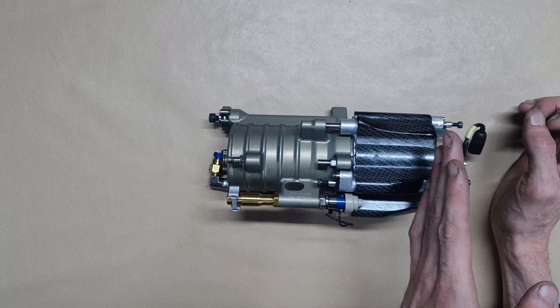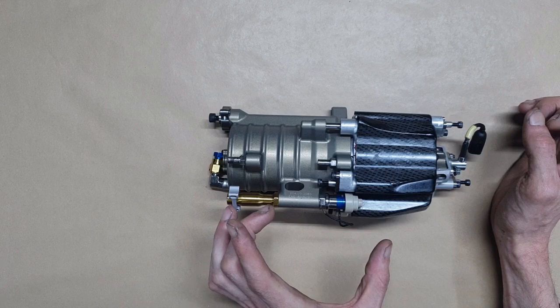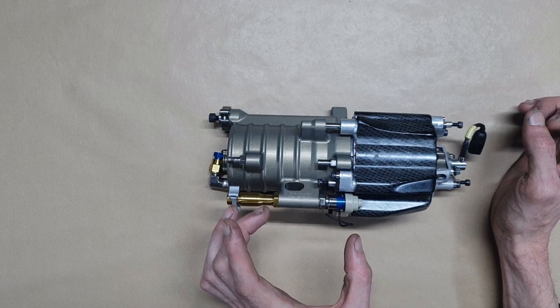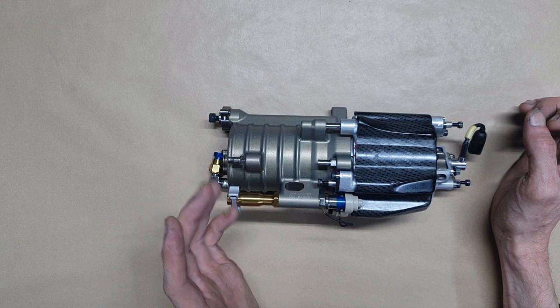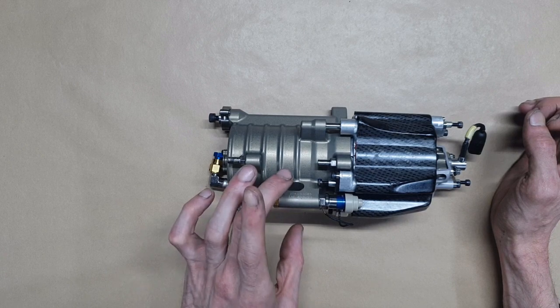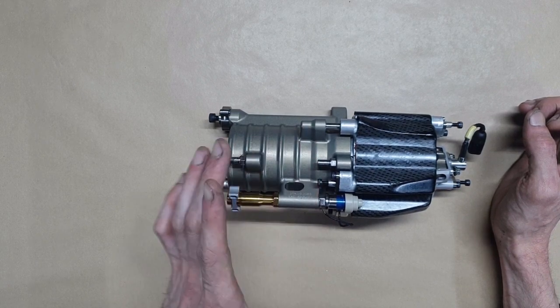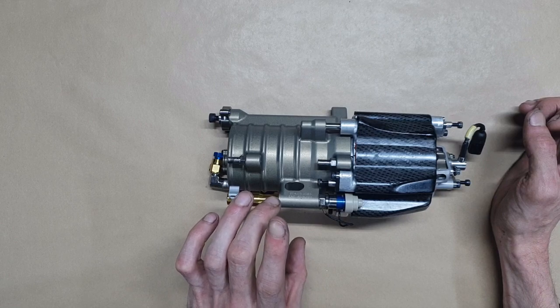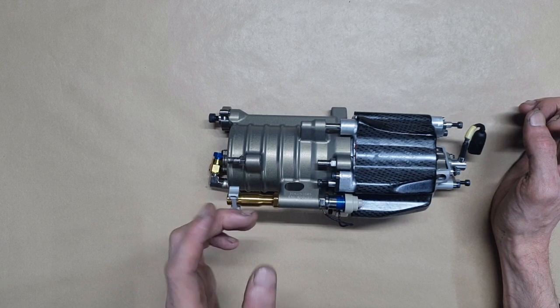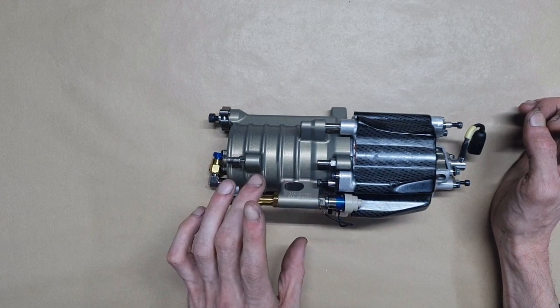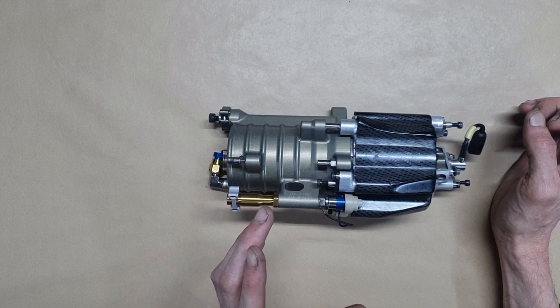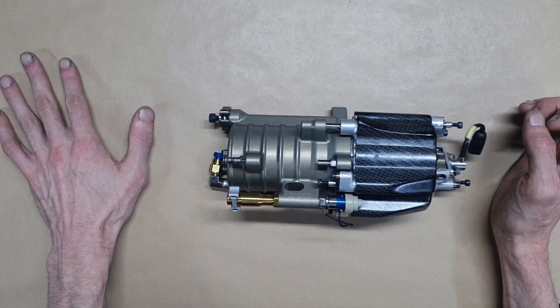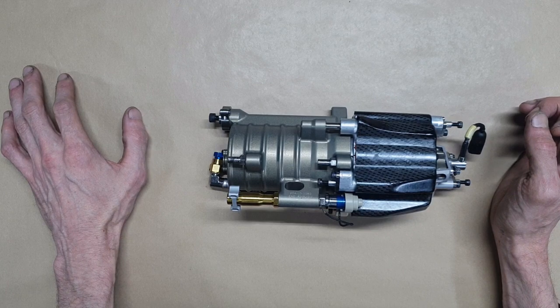As well as that, if you had say 1,000 psi of nitrogen gas behind it, in terms of pressure accumulation it could take 1,010 psi to move it because of stiction with the seal in the bore. So it's not as fast to react, but more reliable, and it can flow more just because of its nature, and generally they can take higher pressure as well.